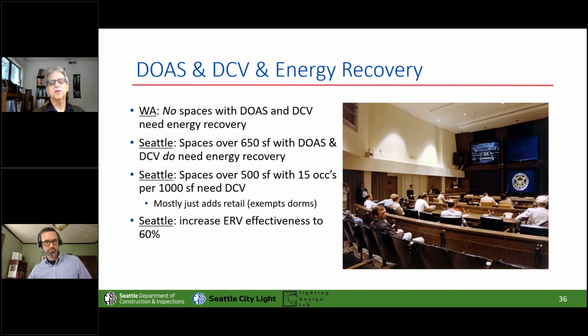For DOAS plus demand control ventilation, in the Washington code, if you've got DOAS and DCV, you do not need energy recovery. In Seattle, if the space is larger than 650 square feet, so even a large conference room would need heat recovery. We just decided that was suitably useful. And in Seattle, if you've got 15 occupants or more per 1,000 square feet, according to the mechanical code, then you need this, and that just adds retail spaces mostly, and then a couple other really tiny occupancies. And finally, we said, yeah, 60% energy recovery is now easily achievable, so we have that instead of 50%.